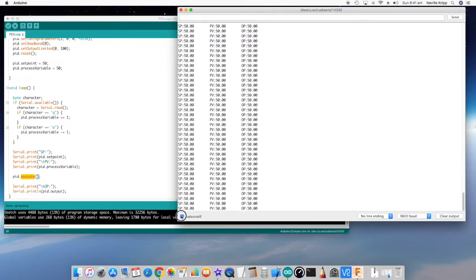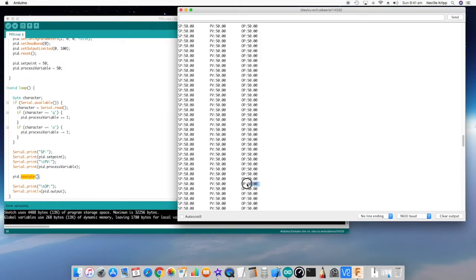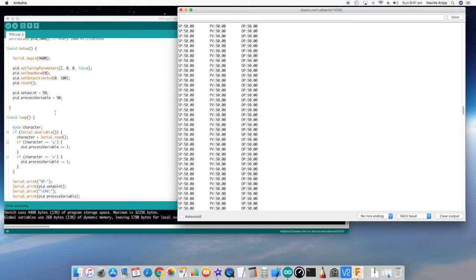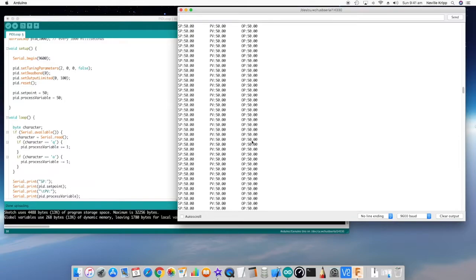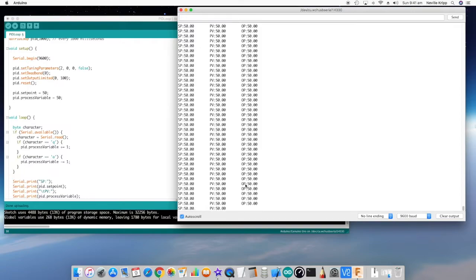As you can see, it's continually streaming out data. We've got our set point set at 50, the process variable starting point of 50, and the output is midway between 0 and 100. At the moment we have tuning parameters of 2, 0, and 0, so we've got a proportional gain of 2. What in effect we should see is if we increase the error, so the difference between the set point and the process variable, the output should vary in a totally proportional manner.